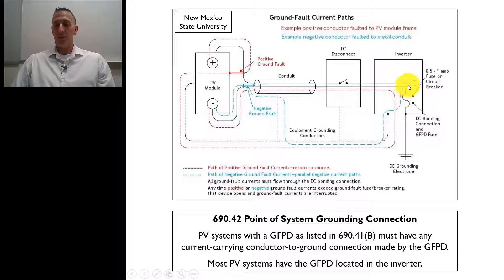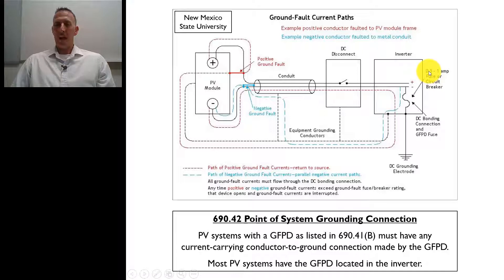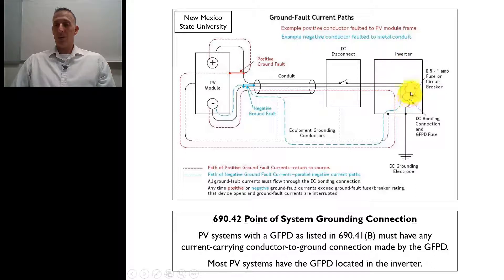The electrons will flow through this fuse back out through the circuit, back up to the positive side. When enough current flows through this — which as you can see in this system it could be a half of an amp to an amp — when more than, say, an amp flows through this one amp fuse, that fuse will blow, disconnect that connection between the negative, that grounded conductor, it now becomes ungrounded, and the inverter will shut down and electrons will stop flowing. That's how a negative ground fault would trip or blow that fuse.